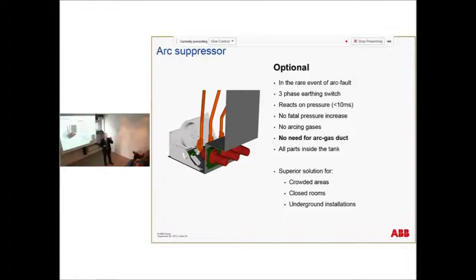In case of an internal fault, this flash will generate heat, which will expand the air. The air expansion will act quickly on this membrane, which triggers this latched spring, which earths all incoming feeders. And in 30 milliseconds everything is over, and this will not burst, like we saw in the video from Kenneth. If it had exploded inside, the smoke and the heat would open and go up to the top of our compact substation. But here, this will stay inside.